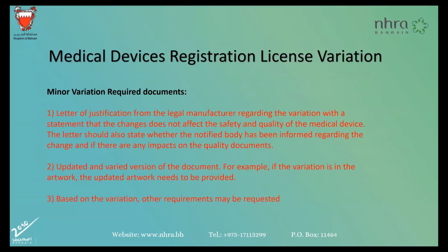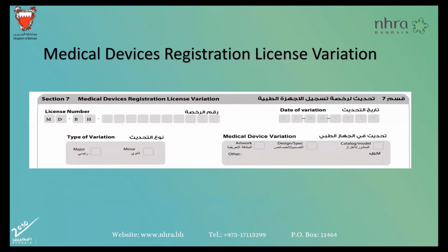The requirement for a minor variation is a letter of justification from the legal manufacturer regarding the variation, with a statement that there are no changes affecting the safety and quality of the medical device. Updated and varied versions of documents, such as the artwork: if it is changed, we need the updated one. Based on the variation, other requirements may be requested. This is the part in the application form which you should fill with the license and type of variation.